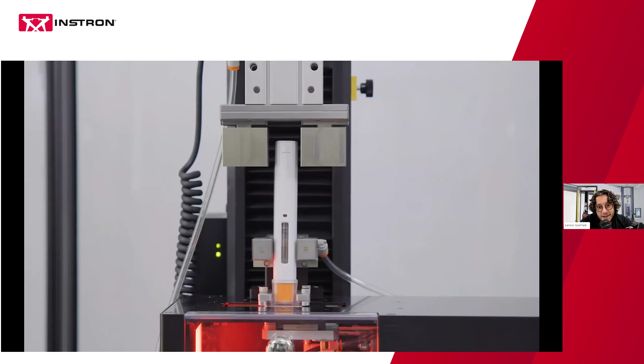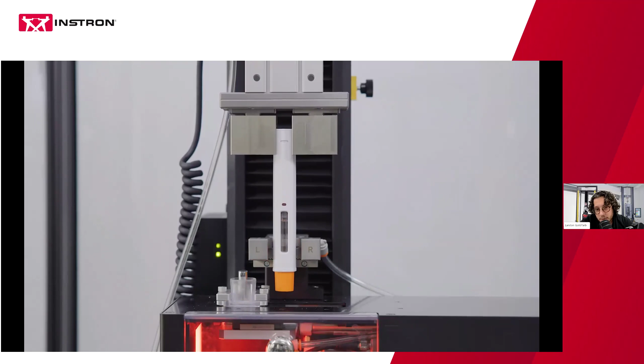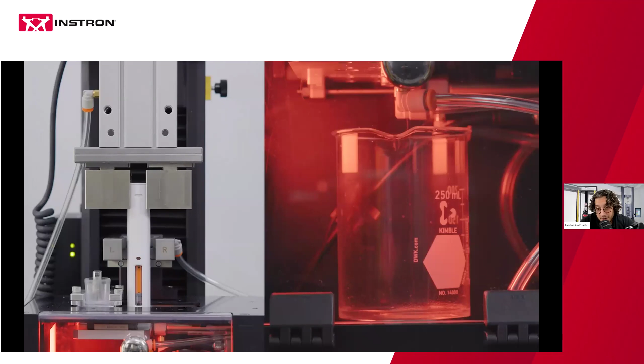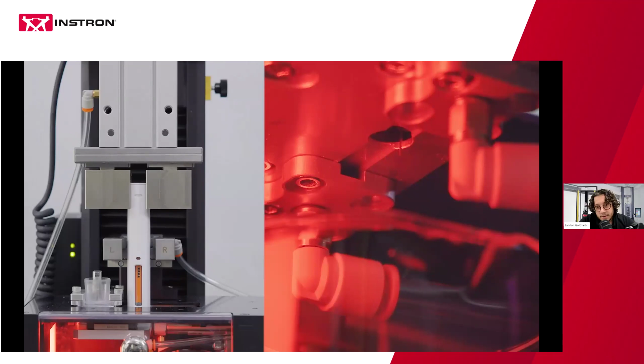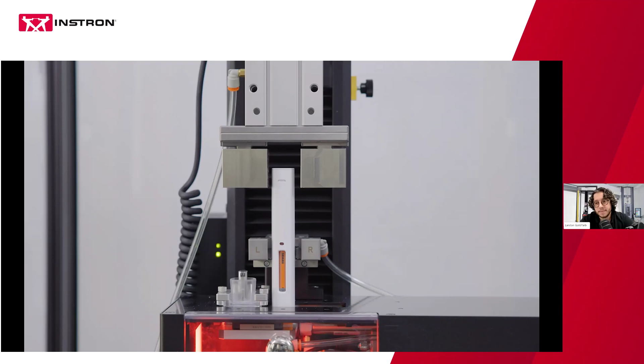So this is just showing a full sequence running. For a two-step device, you're typically looking at a 45-second cycle time to measure all EPRs. So it'll do the cap removal, immediately move the cap out of the way of the device, come down, and activate the device. You'll have all the injection monitoring underneath, which will include the scale, the machine vision camera, and the microphone. You'll have the last drop step to blow the last drop of fluid off the tip of the needle, and then we'll come back up and do the safety check, and then we'll put the device back down. So, like I said, 45 seconds to a minute, dependent on the injection time. And for a button activated device, it could be a little bit longer, a minute 20, a minute 30, just because there are a few more steps to activate it.